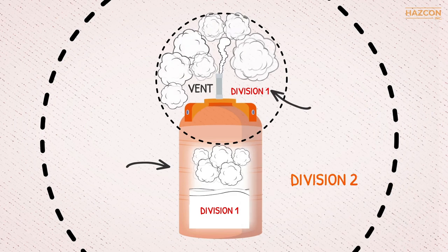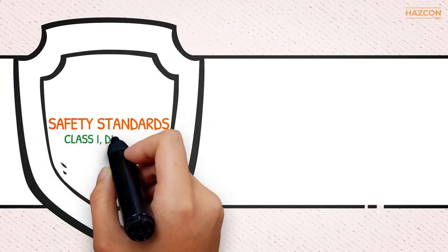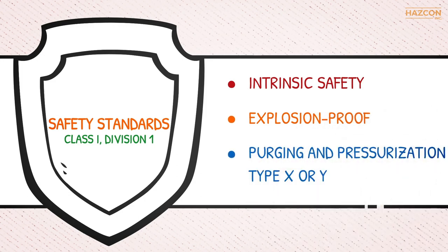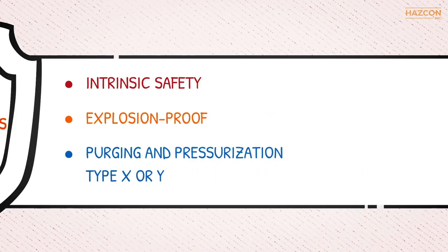In order to be certified as compliant with safety standards for Class 1 Division 1, the product must be protected by one or more of the following three protection techniques: intrinsic safety, explosion proof, and purging and pressurization type X or Y.